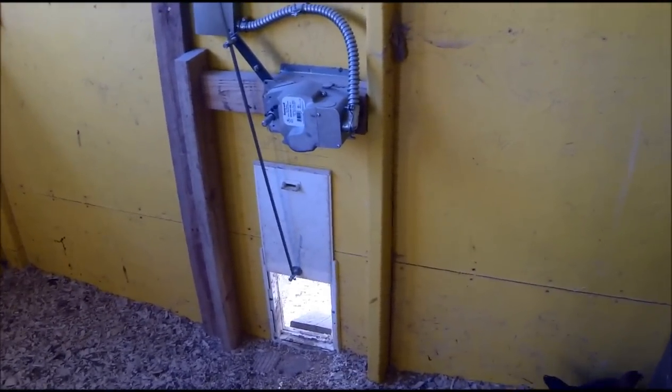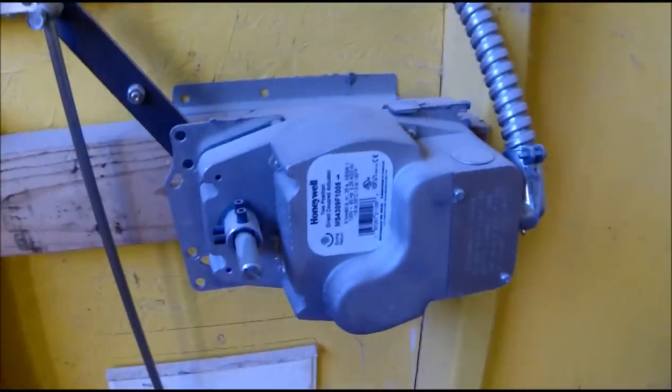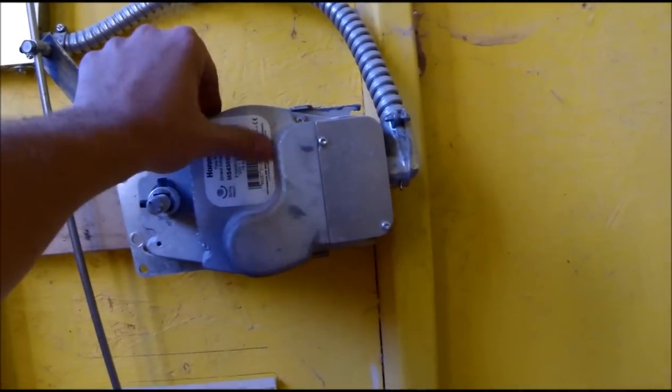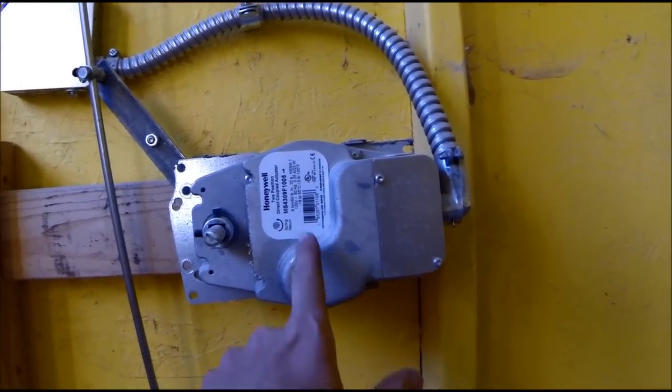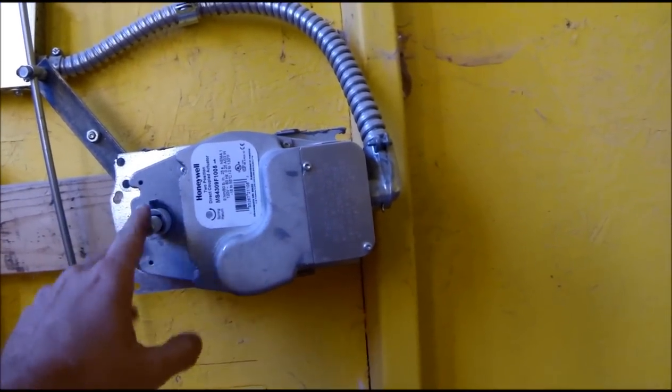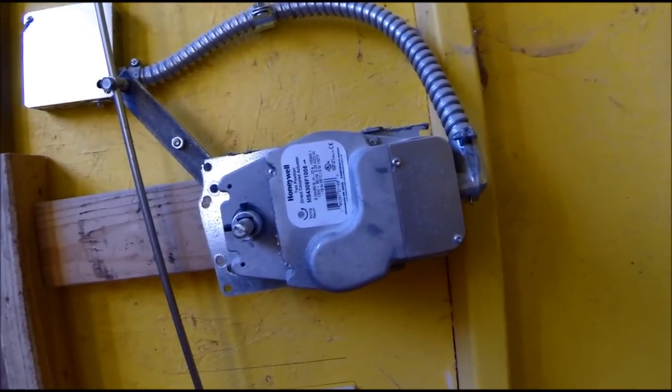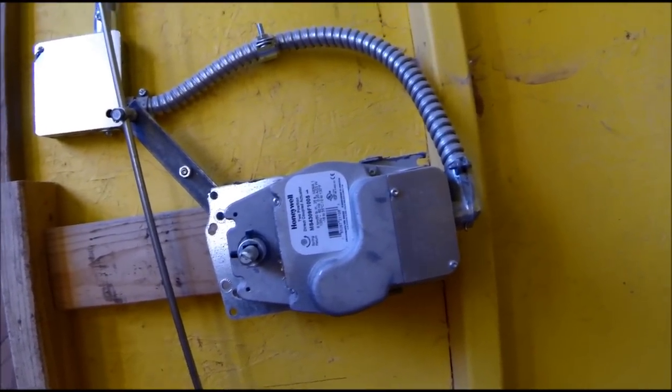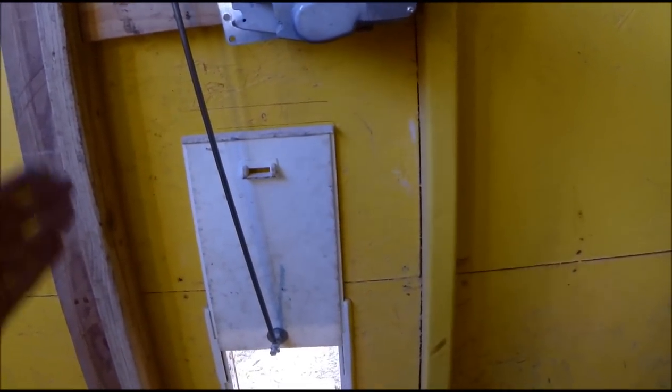All I did is mounted a Honeywell actuator here. This is HVAC stuff, it's a damper actuator. There's the model number. It is just a two position spring return. What that means is there's just a hot and neutral going to it. When you energize it, I've made it so the door comes up and when you de-energize it, a spring takes it down.